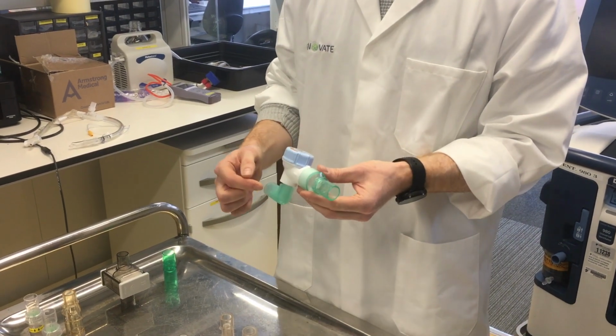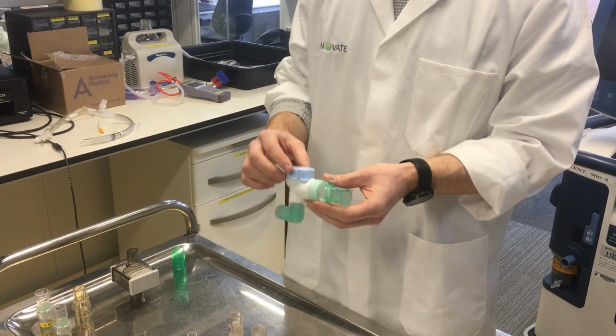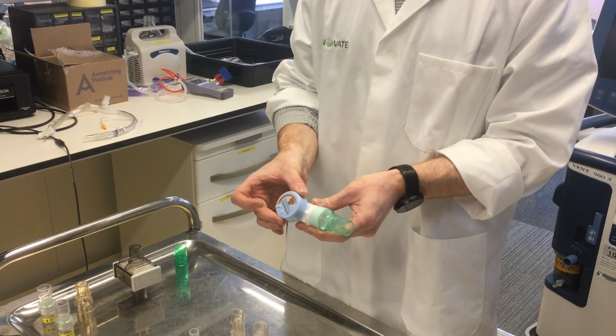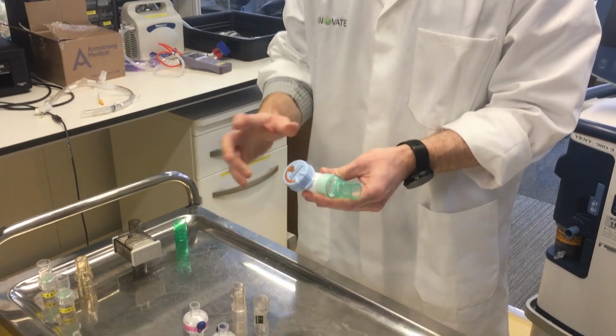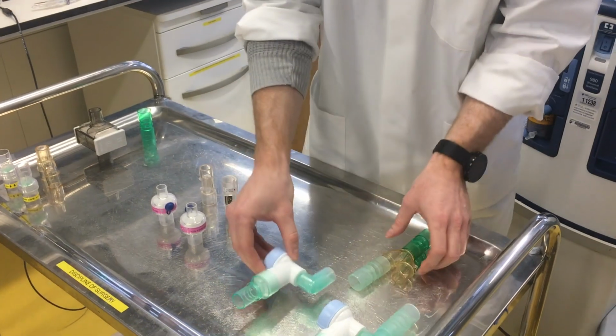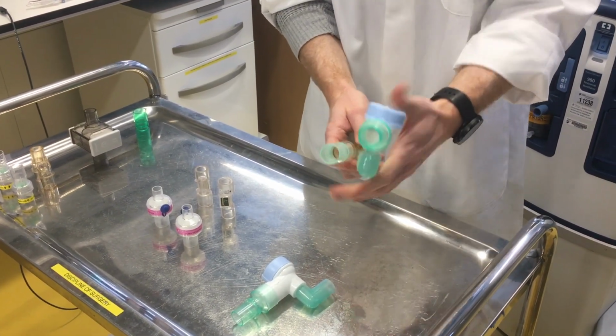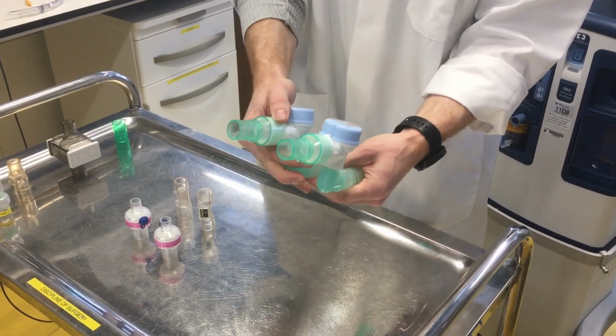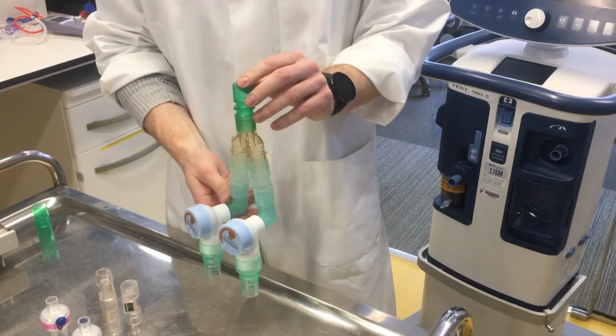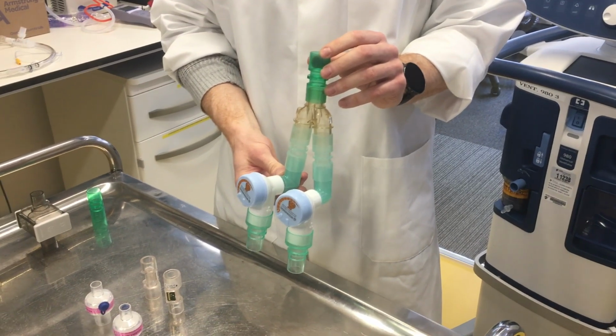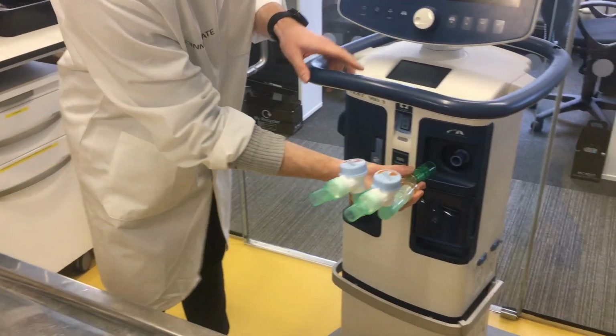In effect, what that does is it brings all the flow through the valve, which can be now used as a variable flow restrictor. So that's in its fully open position there, and now we have two of them. So we connect these via the female to female connectors, one for each patient, and then that is your full inspiratory limb assembly, and that plugs directly into the ventilator.